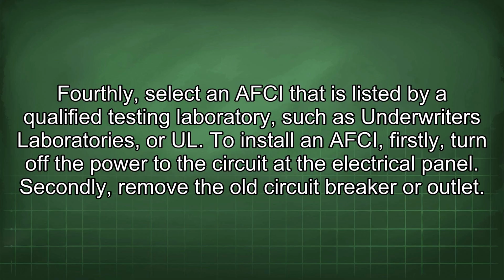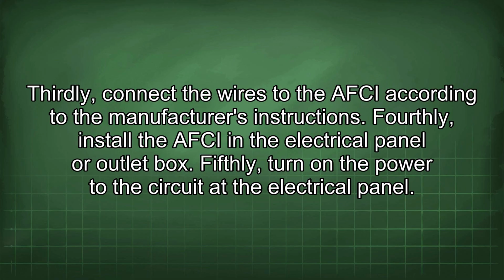To install an AFCI, firstly, turn off the power to the circuit at the electrical panel. Secondly, remove the old circuit breaker or outlet. Thirdly, connect the wires to the AFCI according to the manufacturer's instructions. Fourthly, install the AFCI in the electrical panel or outlet box. Fifthly, turn on the power to the circuit at the electrical panel.